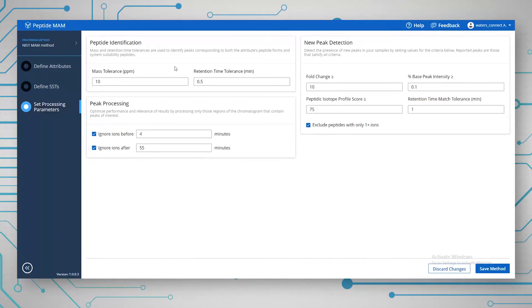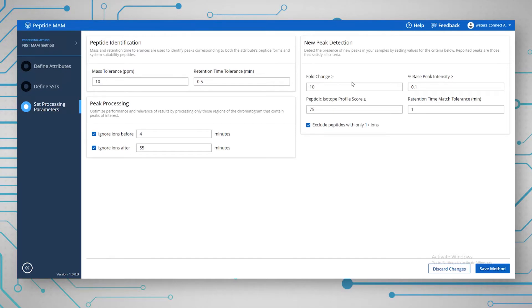The last stage in the method is the processing parameters — not too much to set up here. It's basically just your mass tolerance and retention time tolerance. The peak processing window is a good thing to use — it allows you to ignore ions before a certain part of the gradient and after it, so you're concentrating on the part of the gradient that has the peaks of interest, which also makes the processing more efficient. This is also where you set up the criteria for the new peak detection, though this can be tweaked after the sample run is processed — you don't need to go back to the method to change the new peak detection criteria; you can tune it after the batch has been run.